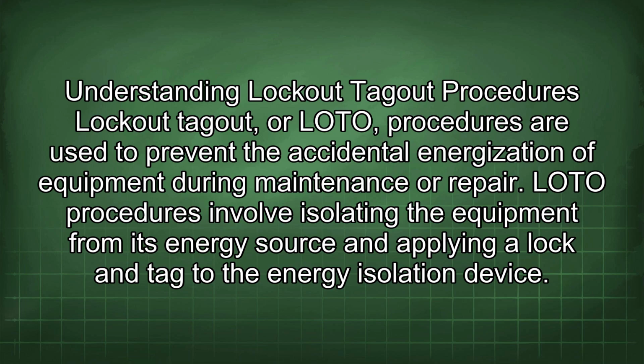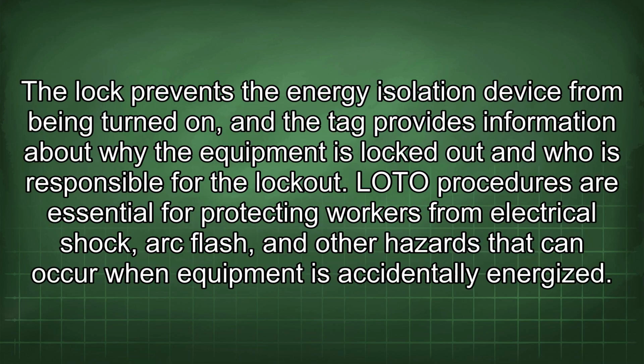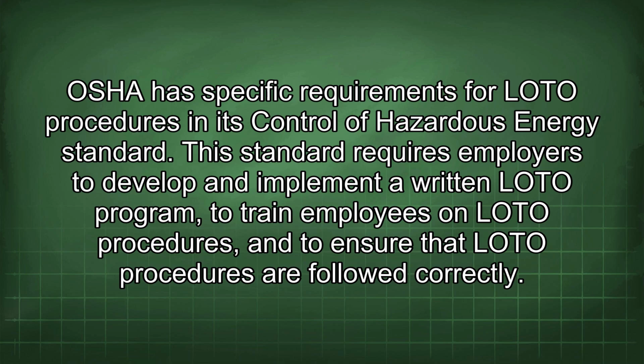LOTO procedures involve isolating the equipment from its energy source and applying a lock and tag to the energy isolation device. The lock prevents the energy isolation device from being turned on, and the tag provides information about why the equipment is locked out and who is responsible for the lockout. LOTO procedures are essential for protecting workers from electrical shock, arc flash, and other hazards that can occur when equipment is accidentally energized. OSHA has specific requirements for LOTO procedures in its Control of Hazardous Energy standard.